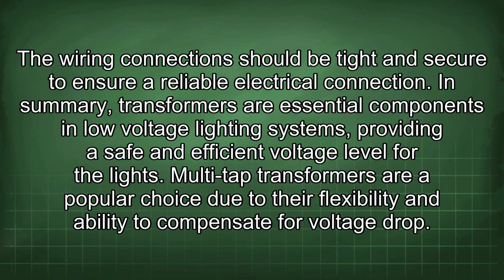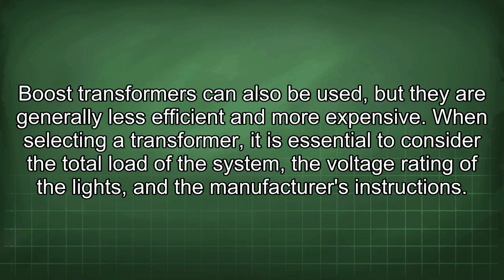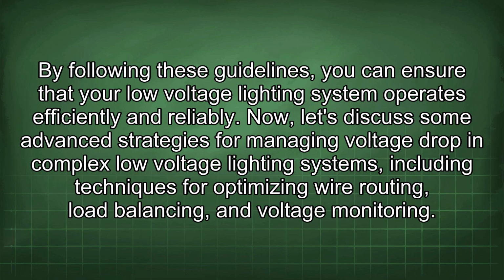In summary, transformers are essential components in low-voltage lighting systems, providing a safe and efficient voltage level for the lights. Multi-tap transformers are a popular choice due to their flexibility and ability to compensate for voltage drop. Boost transformers can also be used, but they are generally less efficient and more expensive. When selecting a transformer, it is essential to consider the total load of the system, the voltage rating of the lights, and the manufacturer's instructions. By following these guidelines, you can ensure that your low-voltage lighting system operates efficiently and reliably.